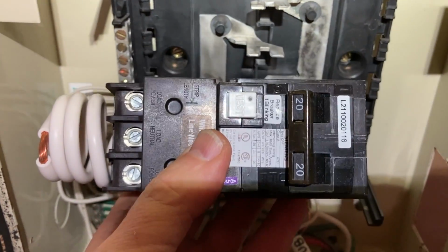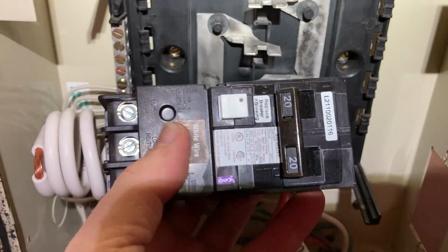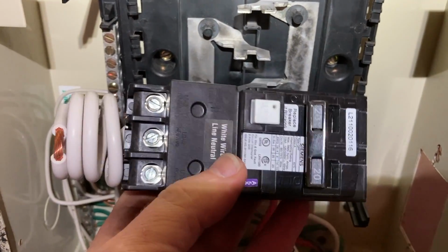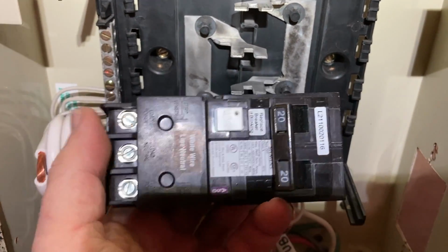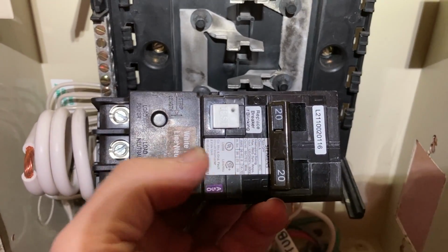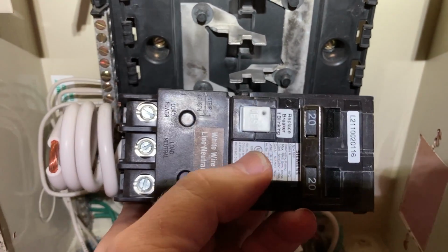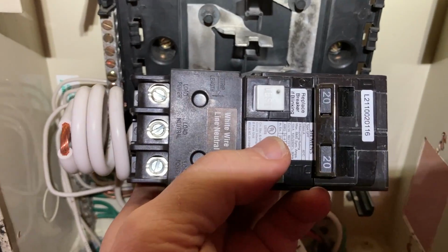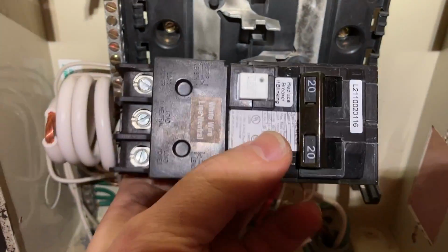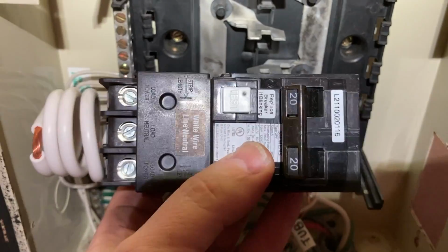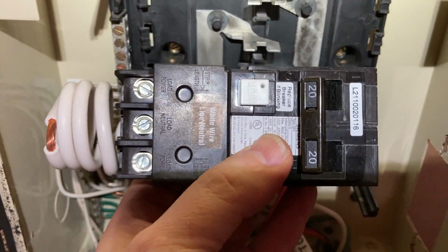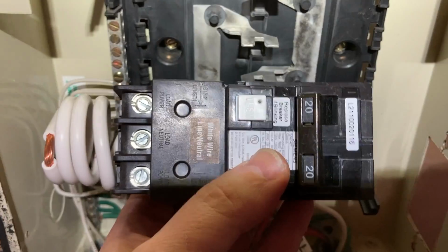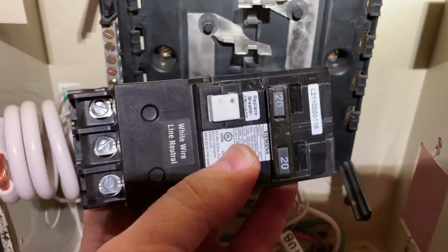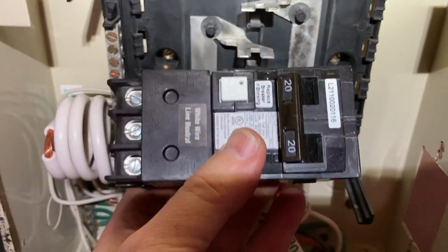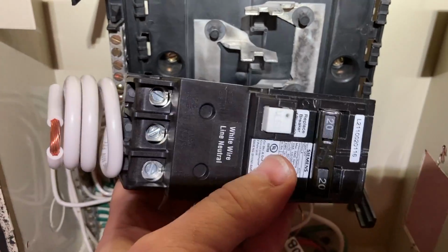Some LM series voltage comparator in here, and some other stuff to make it fail safe. The idea is, if the current is going one way, like out to the load, it induces a magnetic field in one direction, and if it's coming back, it induces the magnetic field the other direction. Ultimately, you want those to cancel out and be 0, so the current going out equals the current going in, to within 6 milliamps. This is a Class A breaker, so it trips if the difference gets above 6 milliamps.